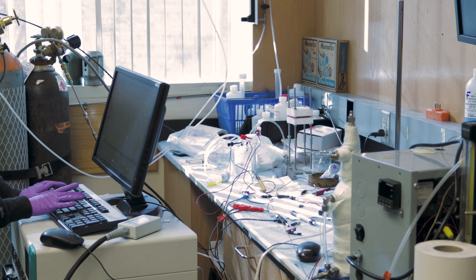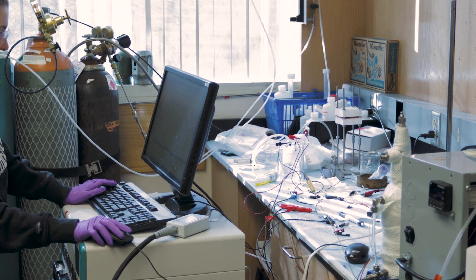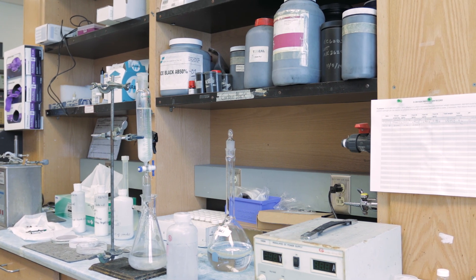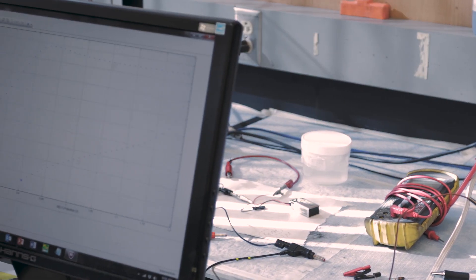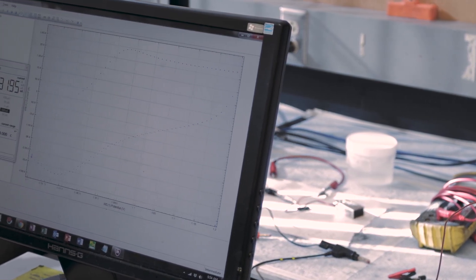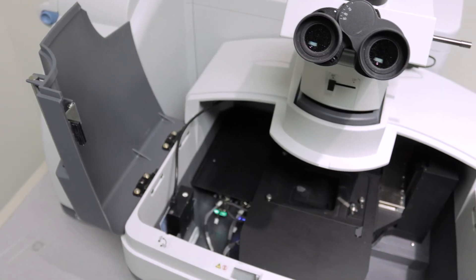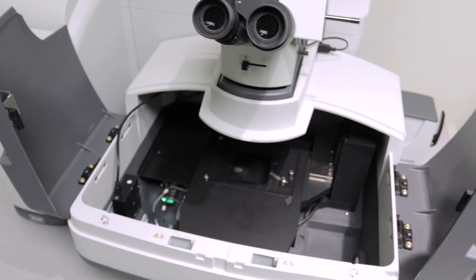We have a whole host of electrochemical techniques which we use, ranging from simple charge-discharge to very complicated routines including electrochemical impedance techniques. All of that is then tied into the spectroscopy, and that close correlation between the two is what we use to glean materials properties. As we move along, we are trying to do the spectroscopy under in-situ operating conditions, and there are certain aspects of how that instrument interacts with our cells which is very critical — and that's where our partnership is so effective.